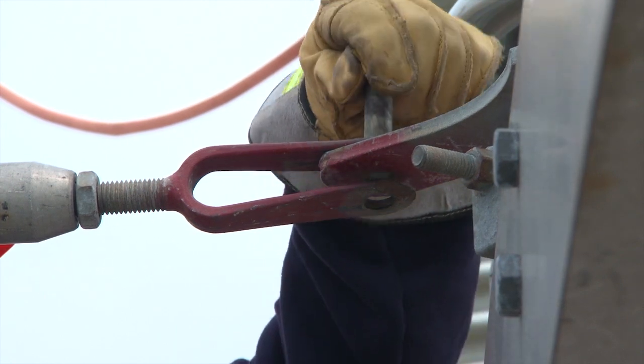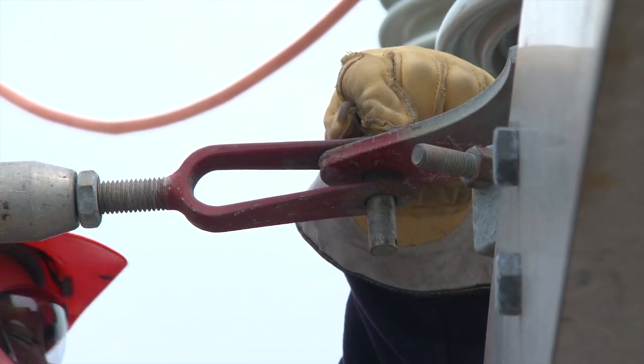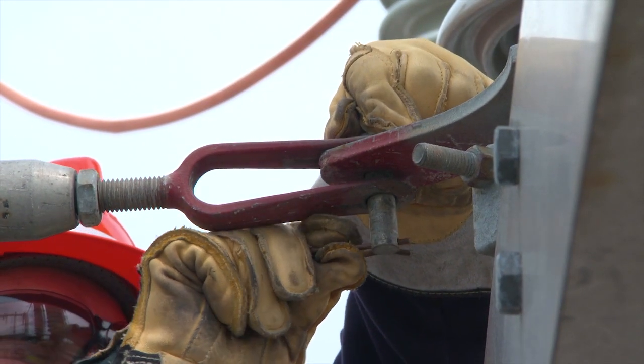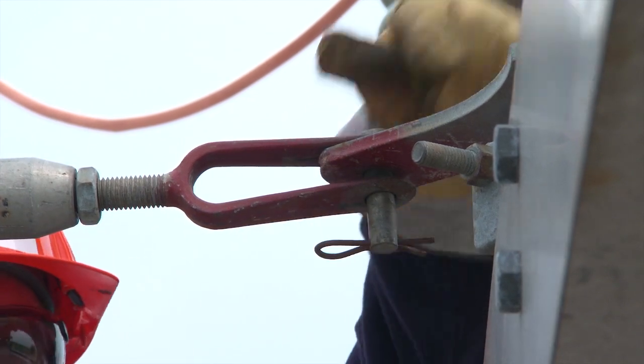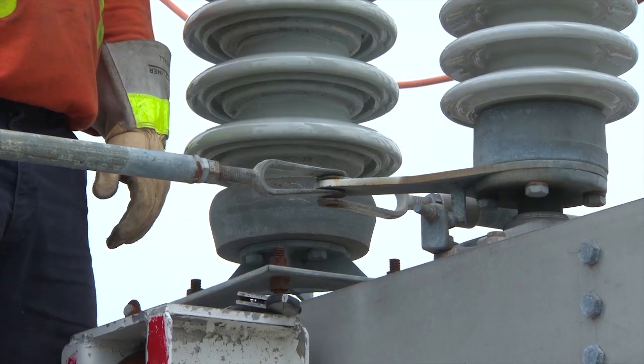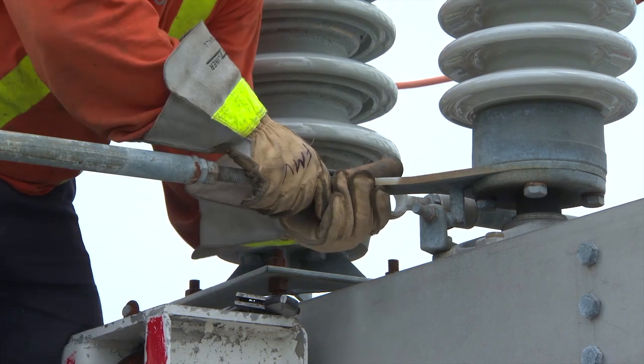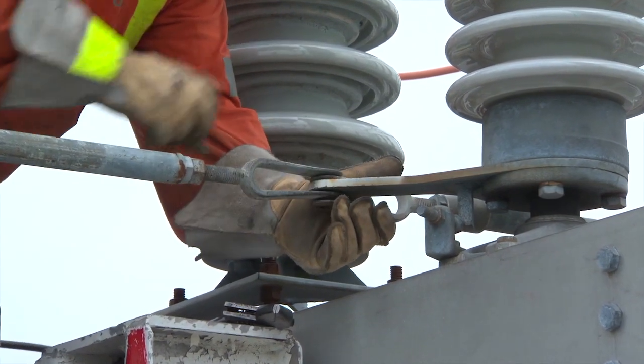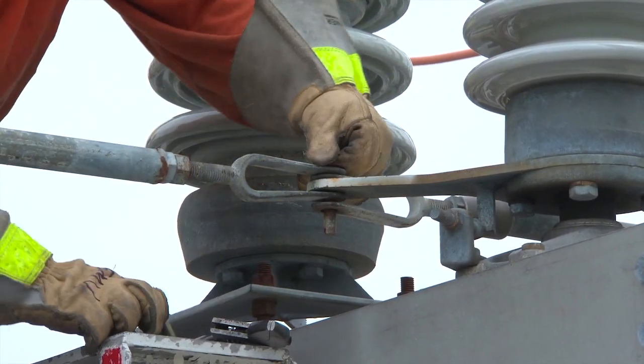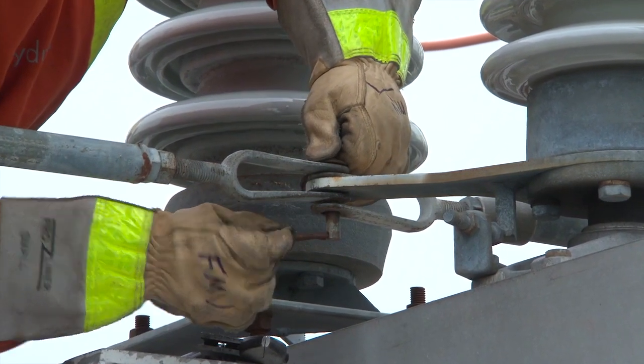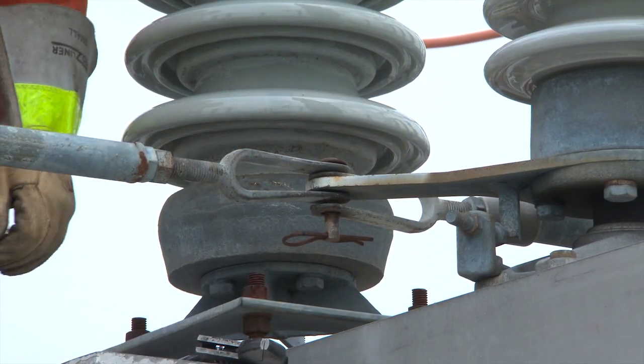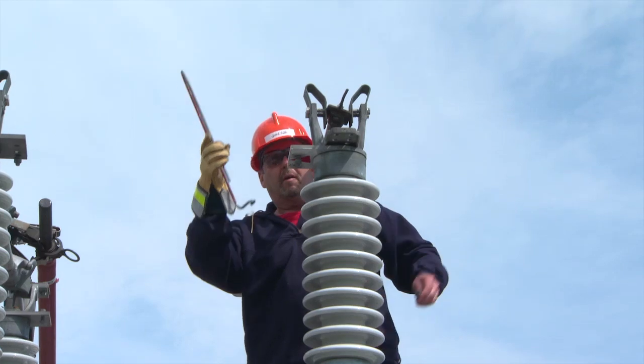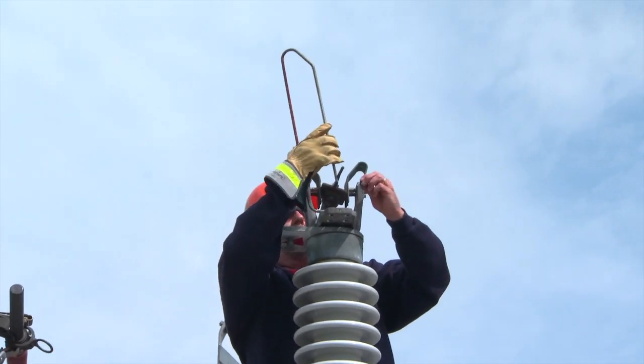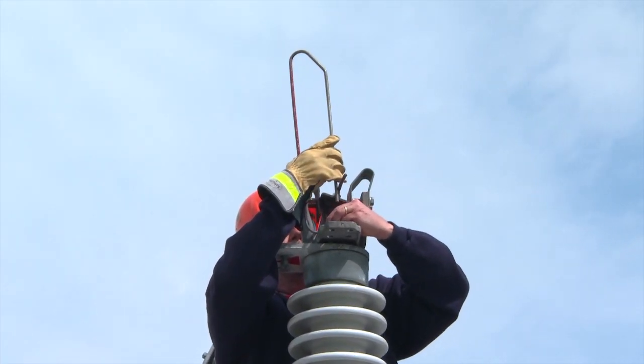Ensure that both white ends meet up on the center paddle. Then proceed to the blue phase, where you can use the switch operating handle to align your final pin with the center paddle. The operating rod ends are color-coded to make installation easier and maintain switch alignment. Finally, install the arcing horns on all 3 phases.